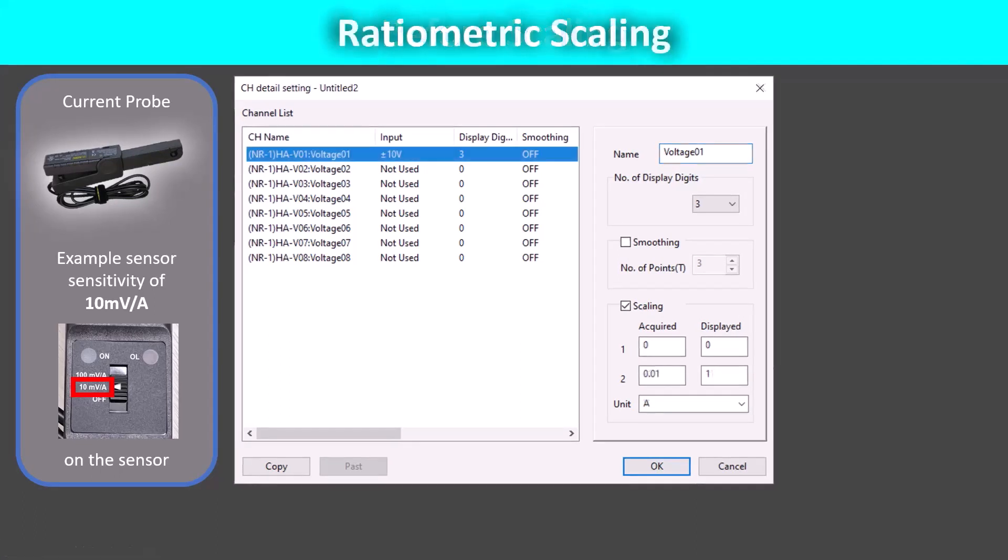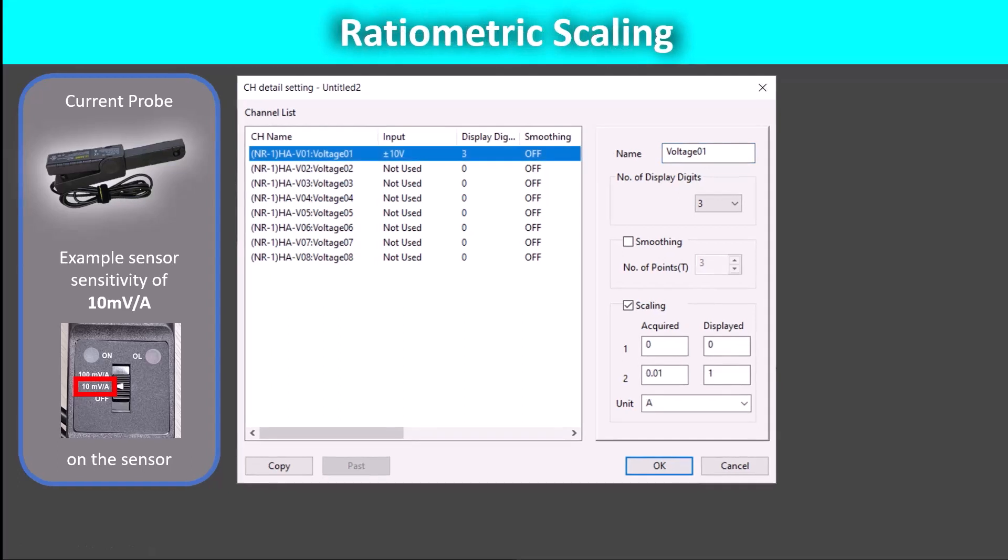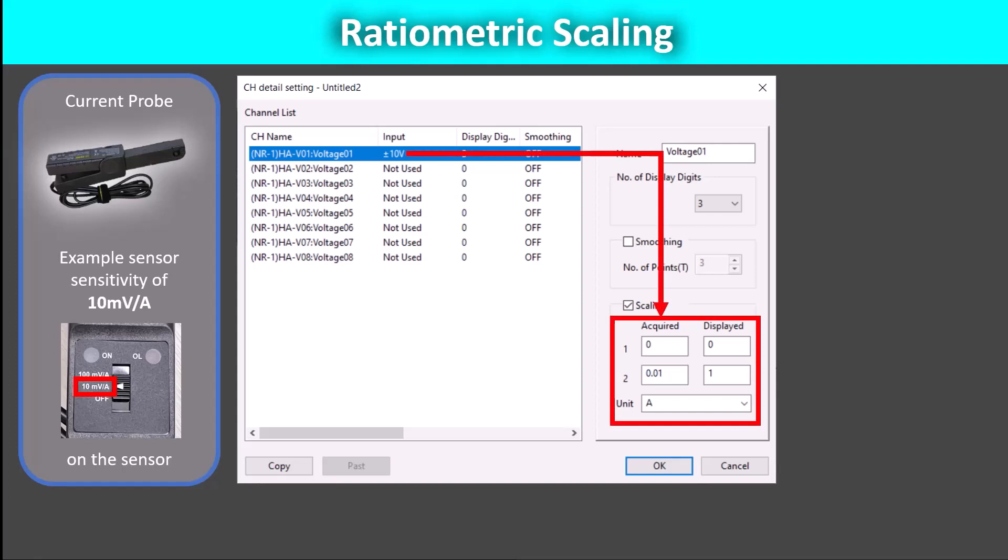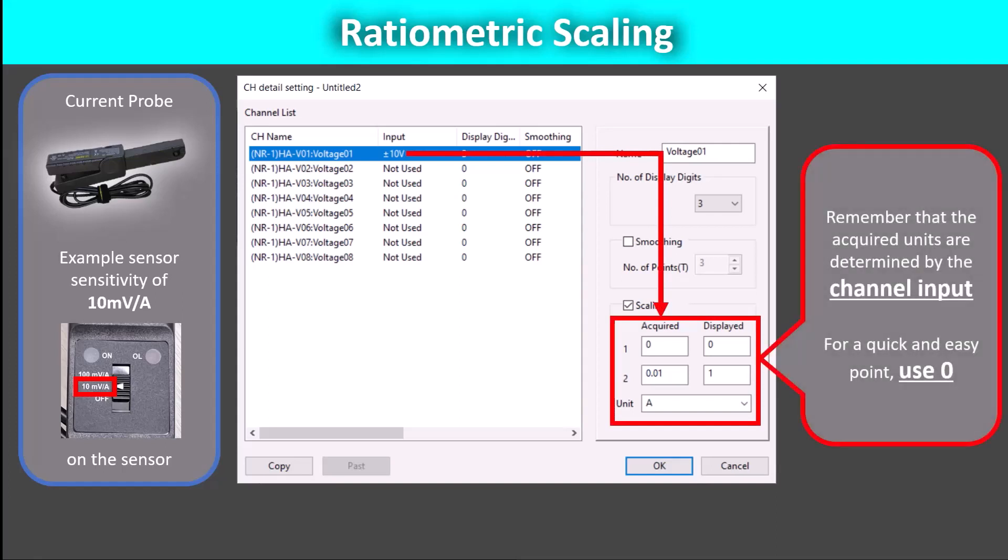The currently selected option is the 10 millivolt per amp setting. For this setting, we will still set zero volts equal to zero amps in point one. Being careful to notice that the channel input units are in volts, we will set point two to be one hundredth of a volt is equal to one amp. This means the same thing as the sensitivity in millivolts.